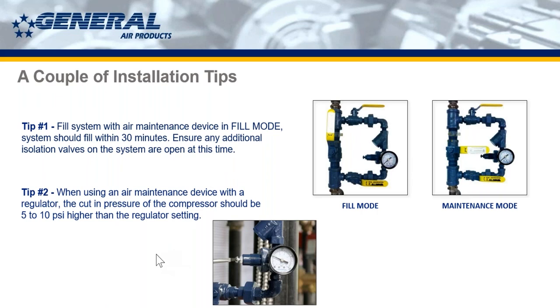Another tip here, when using an air maintenance device, the pressure from the compressor should be 5 to 10 PSI higher than what your system pressure is. So if you're holding the system at 40 PSI, kick your compressor up to at least 45 to 50 PSI and let the regulator do the work to hold it back. It will work fine.